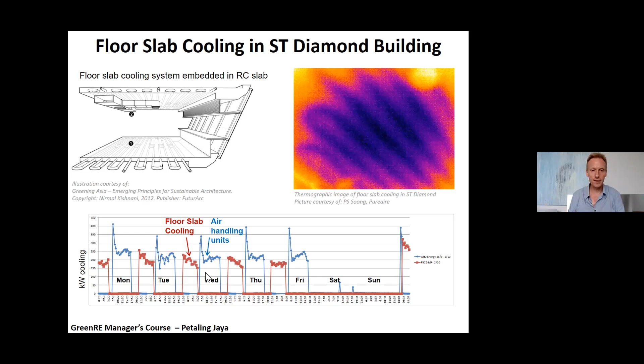in those kind of situations. And here we were lucky to do some measurements of the temperatures because everyone is always worried, does water condense on the ceiling? And the answer is no, because the dew point is down here. It's about 17 degrees. And you can see that during normal operation, which is here, the ceiling temperature, the red one, gets down to about 21 degrees. So it never crosses the dew point, which is 17.